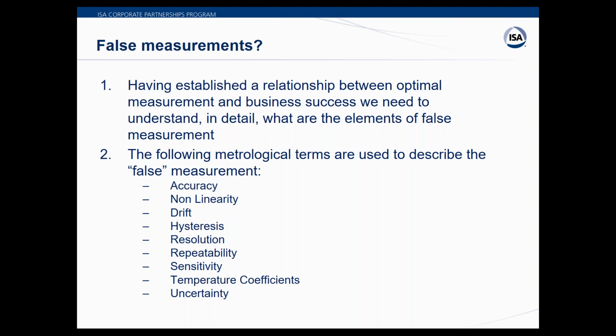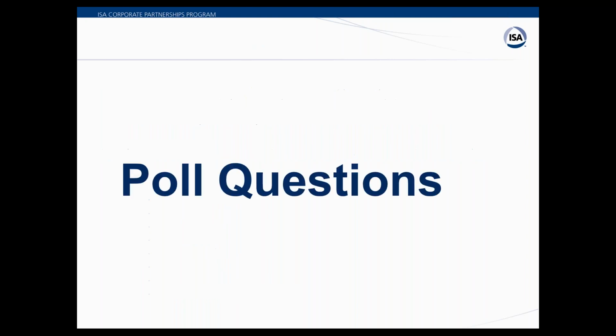When you're looking at readouts or gauges, what's the resolution that you can see? And what is the repeatability of the instrument? If you cycle it a couple of times, do you see non-repeatable results? And how sensitive is the instrument, especially to temperature? And then finally, here's uncertainty down at the bottom. All these things and more can contribute to poor quality or off quality when it comes to making measurements. All right, so that's my introduction.